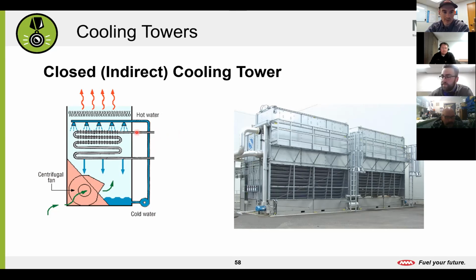Well, it's going to come into this pipe here, go through and lose heat because we have, basically, an auxiliary water loop. We have a sump here of cold water that has a pump on it that takes that cold water to the top and then showers water down over the heat exchanger. So now you have your hot condenser water going through this metal tube that is rejecting heat through the metal to the outside water, and we're evaporating a lot of that water we're pulling from the sump. They're two separate loops. We're just raining water down on one.